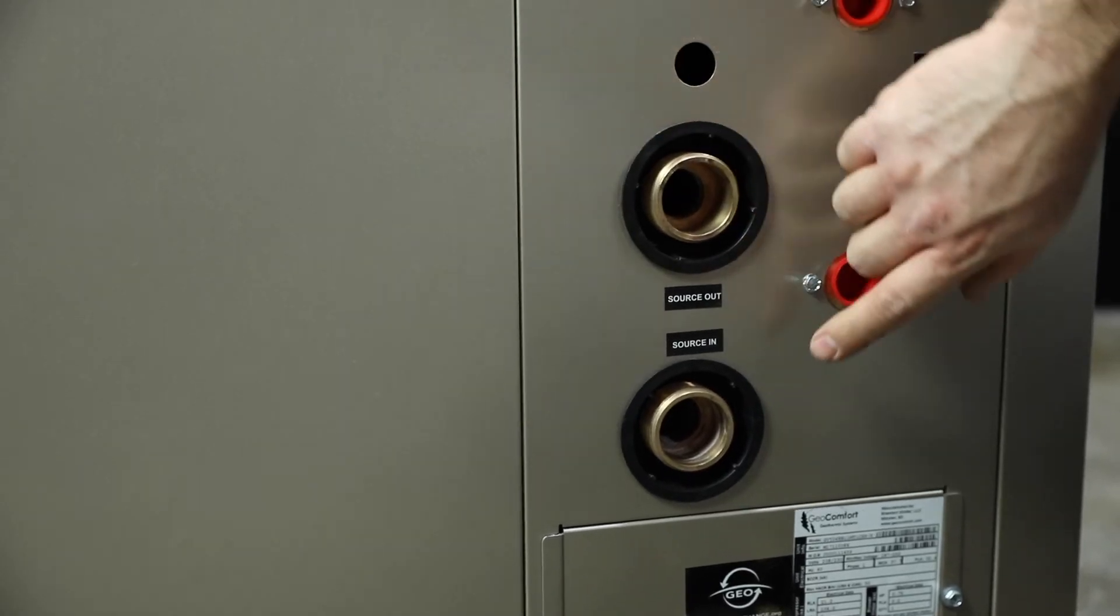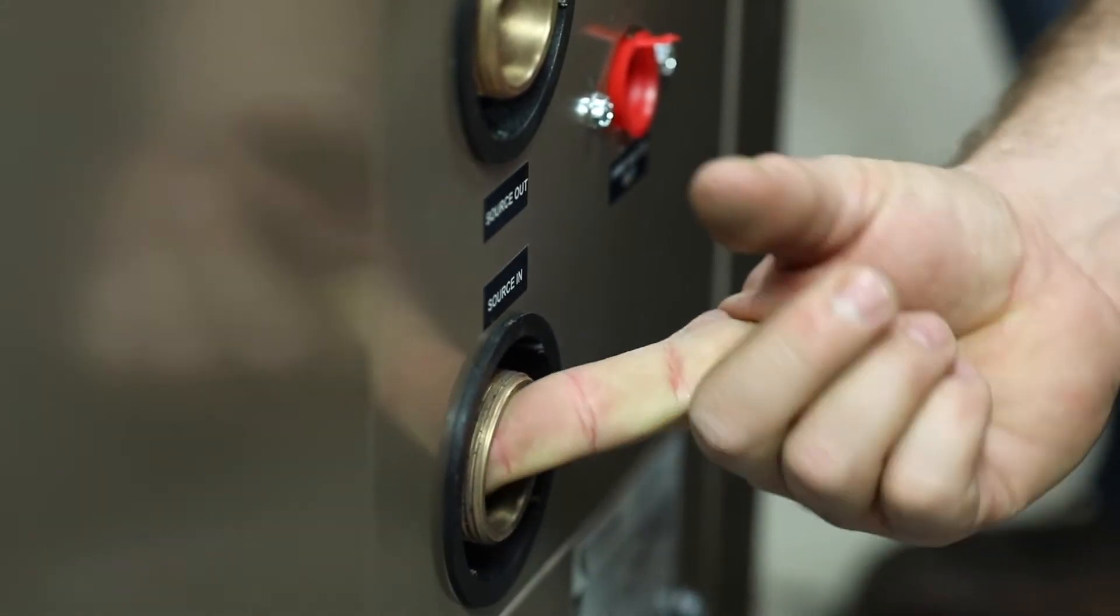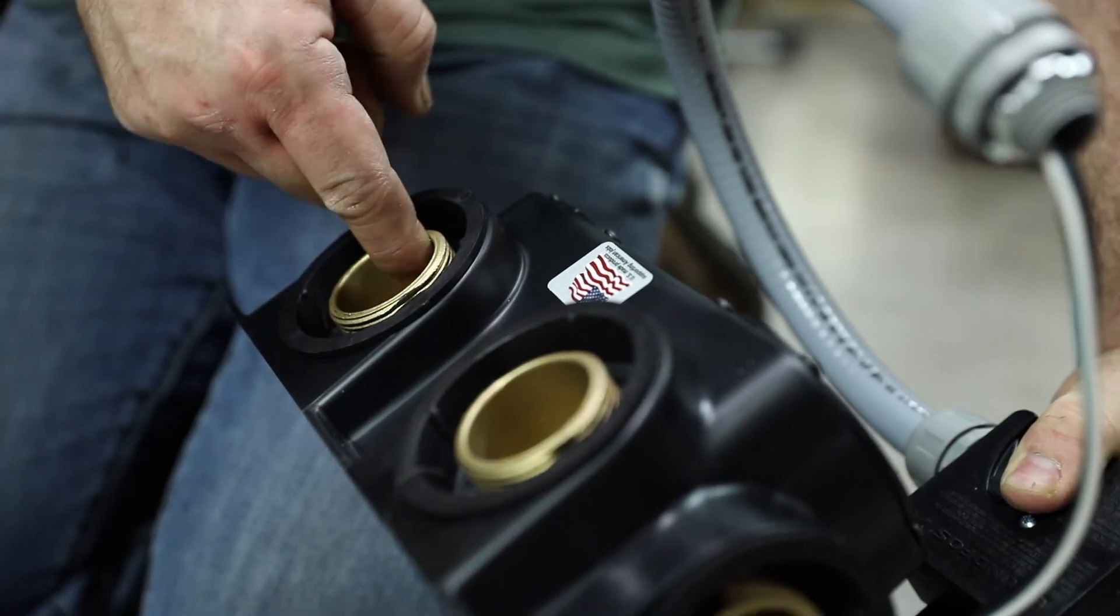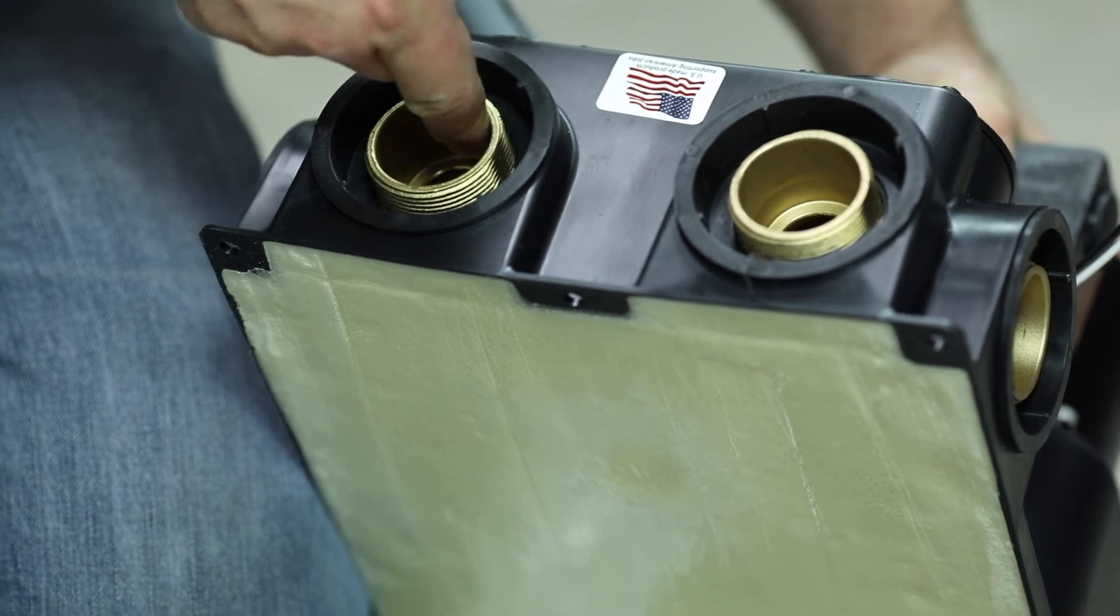Inspect all o-rings and confirm they are in good condition. It is important to lubricate all o-rings on both ends of each fitting before connecting. Be sure to lubricate the inside of both fittings on the unit as well as those on the female threads of the flow center.